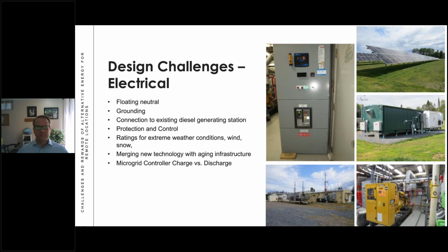There were some potential protection and control challenges as well. At first, we had a lot of nuisance tripping with the breaker due to the coupling of the two systems together, due to the imbalance of the ungrounded system. And that reference point and the sensitivity of the trip settings had to be adjusted to minimize those nuisance trips while still protecting the system. In addition, the sequence of the breaker closing operation of the ungrounded system and the grounded system, rather, with the main intertie breaker also helped resolve this issue.